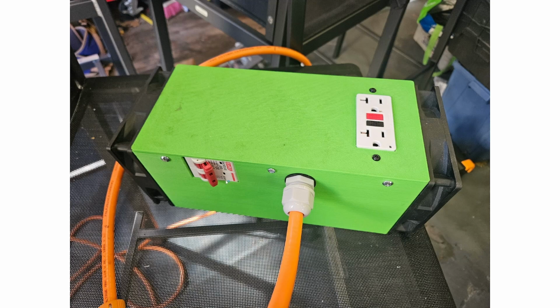This is a 1000 volt rated, DC rated circuit breaker, 10 amps. 10 amps at 400 volts is about 4 kilowatts. I'm certainly not going to pull more than 4 kilowatts.